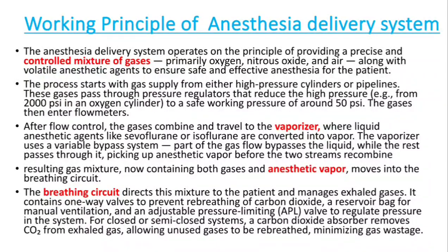Then the gas will pass through the vaporizer, where the liquid anesthetics will be turned into vapors. Then it is delivered to the patient. The gas moves through the breathing circuit and finally reaches the patient. The one-way valve keeps ensuring that everything flows in the right direction. Then there is scavenging: any leftover gases are safely expelled through the scavenger system.